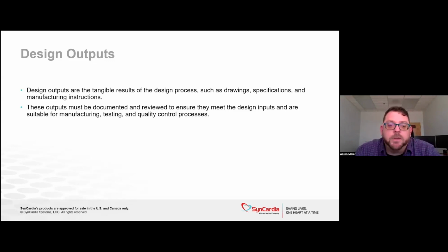One thing I forgot to mention is at all steps in this process is document. Everything you do has to be documented. If it's not documented, it didn't happen. So document your inputs, document your design outputs, you document your requirements, your planning. If you have to deviate, if you change your plan, make sure you document these things because that becomes part of the history of the design of your device.